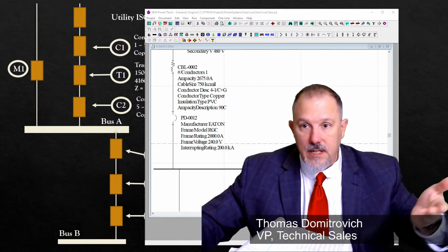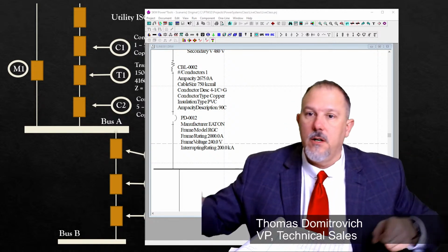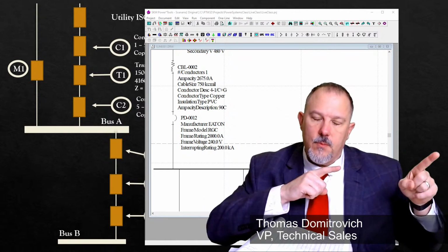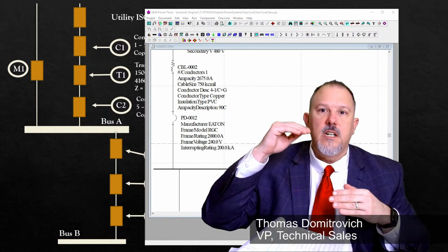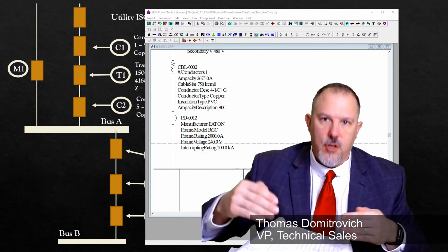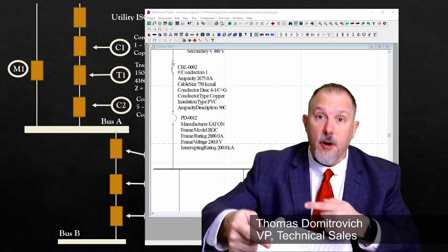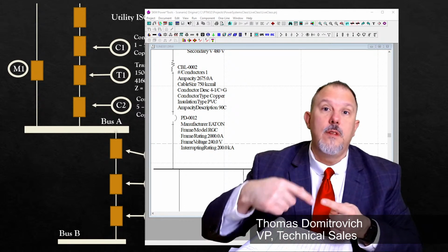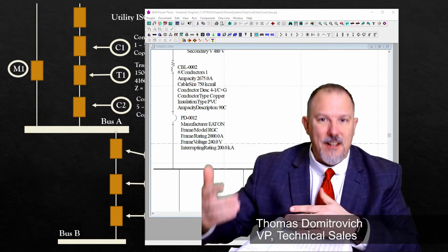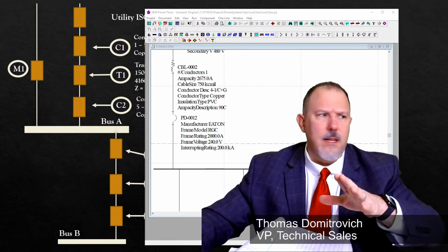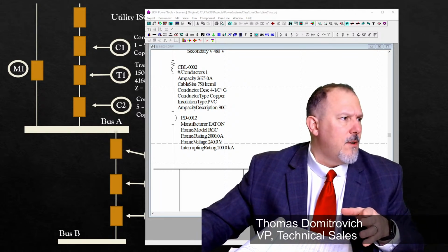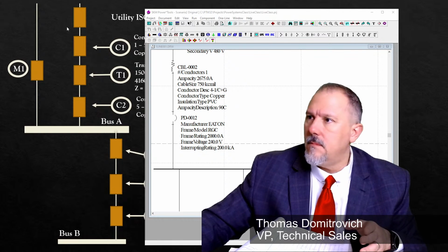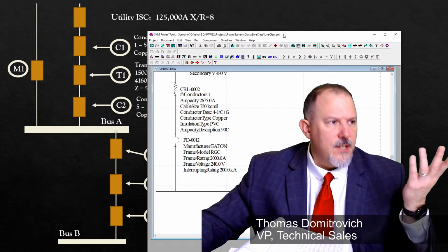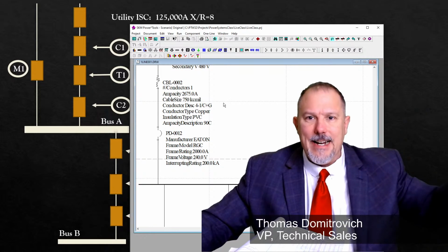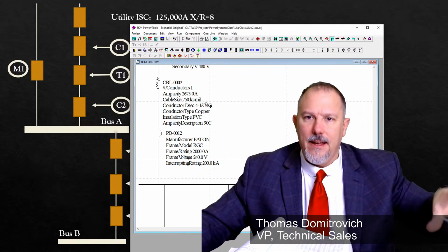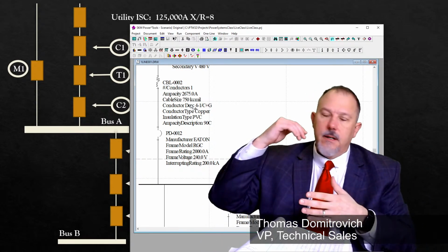And again, the reason that this is going to be a little higher is because I don't model in that spreadsheet the conductor on the primary of the transformer. And I didn't include the X to R ratio of the transformer. I didn't include the X to R ratio of the utility. Or I did do the utility X to R. What was the X to R? 8? Take a look. Yeah, X to R is 8. So I'm a little bit high on this by 70 some amps. But again, I didn't model that primary.